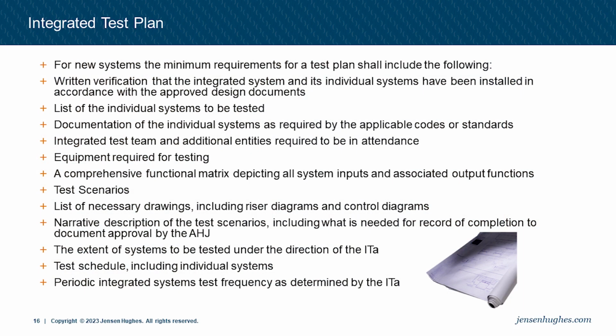Integrated testing plan. For new systems, the plan is supposed to include, and here's the laundry list, written verification that the systems have been installed in accordance with the approved design documents, the list of individual systems to be tested, documentation of the individual systems per the applicable codes or standards, who the integrated testing team is, equipment required for testing, and a comprehensive functional matrix depicting all system inputs and associated output functions. So this is a big one. This is all the things that you're trying to verify, input and output wise, between the various systems. Then test scenarios, so all this stuff is driven by creating test scenarios to drive those inputs and outputs that you're looking to verify.